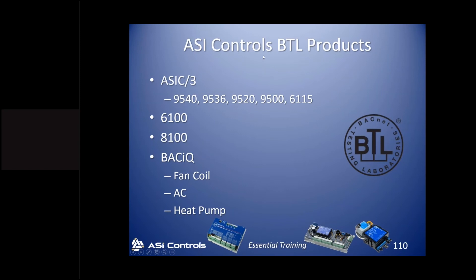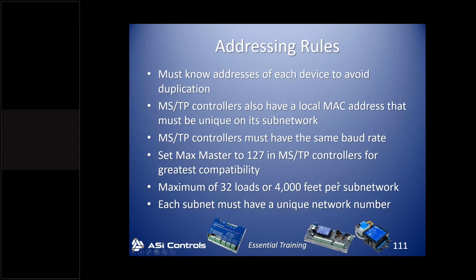This is the summary of the different types of controllers we have with BACnet listings. Just to point out that the BACnet settings information is also here in the slides — the BACnet Device ID is its BACnet address. When servicing a BACnet system, especially with non-ASI controllers, it's important to know all BACnet addresses on the entire network. If you ever add a controller, make sure it doesn't have an address already in use, because duplicate addresses cause communication problems.